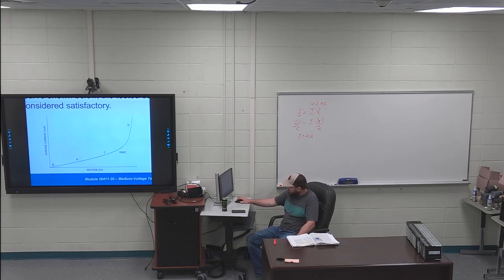So they test at A, increase voltage, let it sit at B, still good there, steadily going up, still good at C. As soon as it starts to turn up, this is called the knee right here. This is where the insulation is starting to break down, so they can test or say this cable is good for up to wherever they determine the cutoff is, well before the knee.